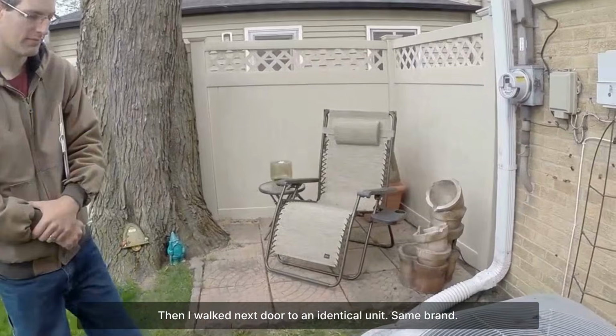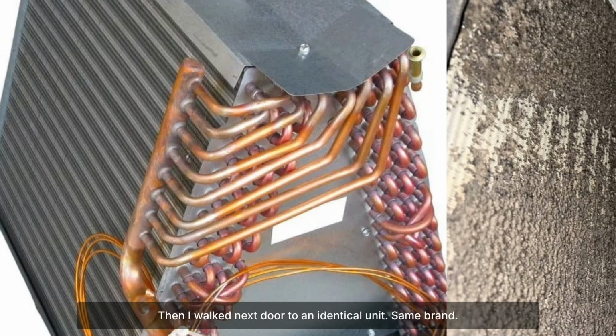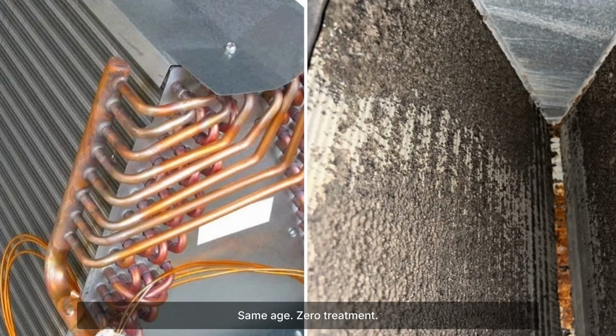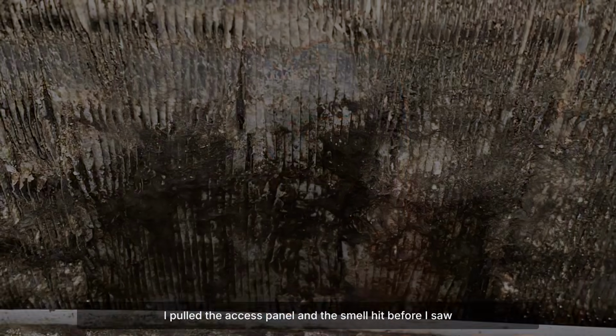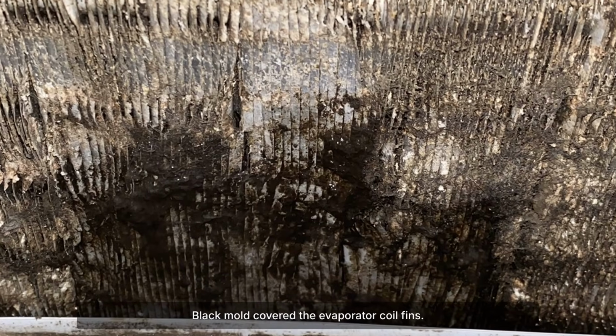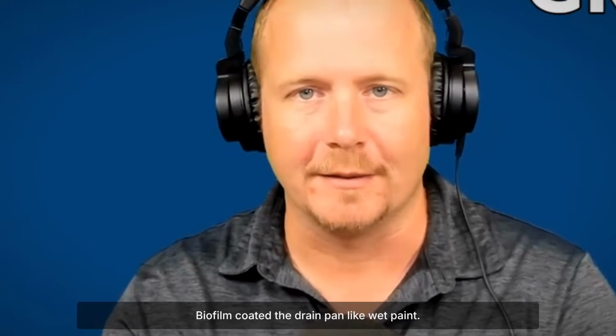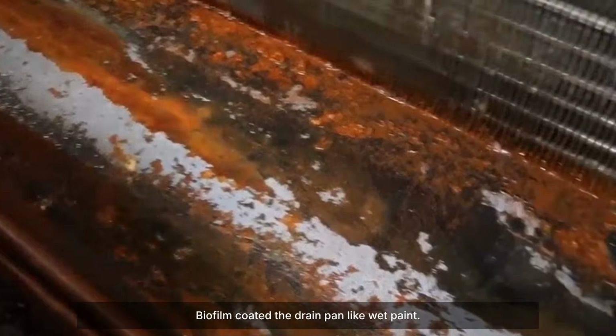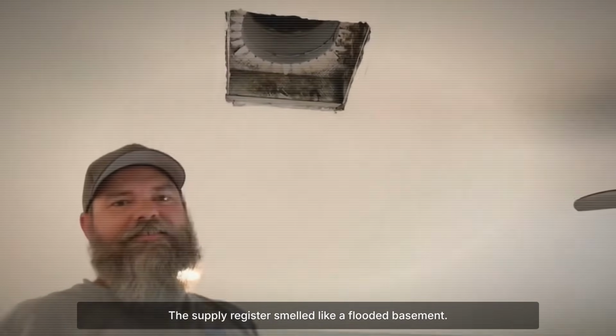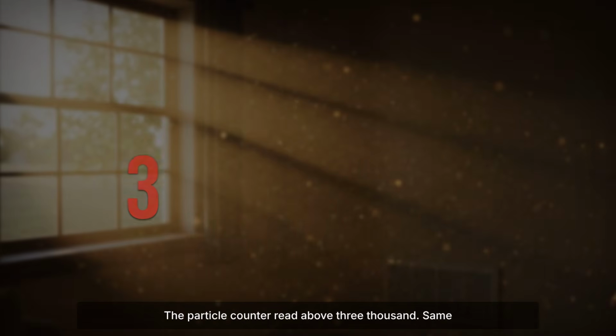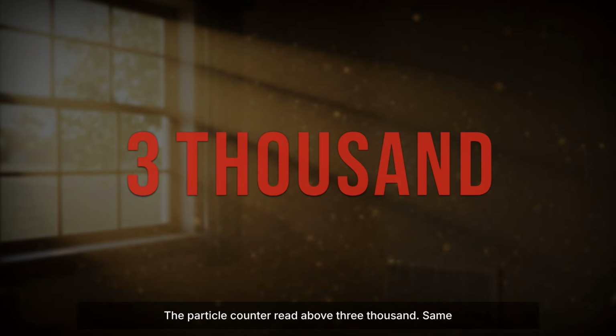Then I walked next door to an identical unit. Same brand, same age, zero treatment. I pulled the access panel and the smell hit before I saw anything. Black mold covered the evaporator coil fins. Biofilm coated the drain pan like wet paint. The supply register smelled like a flooded basement. The particle counter read above 3,000.